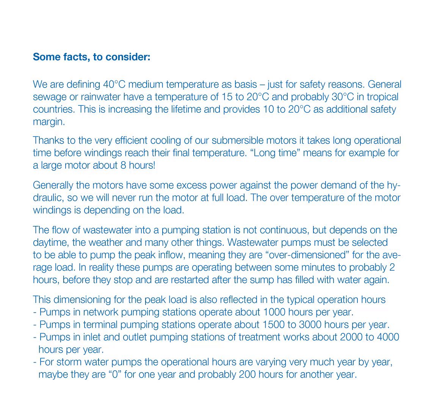The flow of wastewater into a pumping station is not continuous, but depends on the daytime, the weather and many other things. Wastewater pumps must be selected to be able to pump the peak inflow, meaning they are over-dimensioned for the average load. In reality, these pumps are operating between some minutes to probably 2 hours, before they stop and are restarted after the sump has filled with water again.